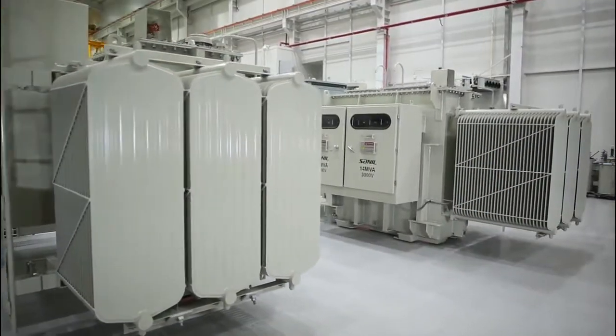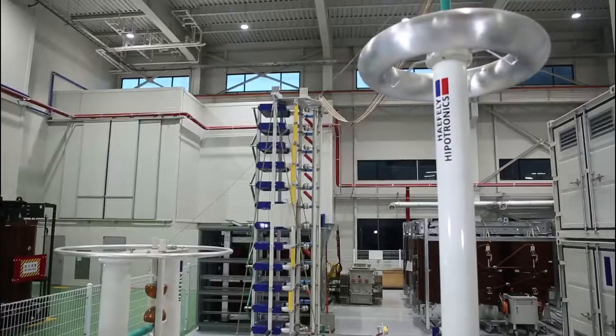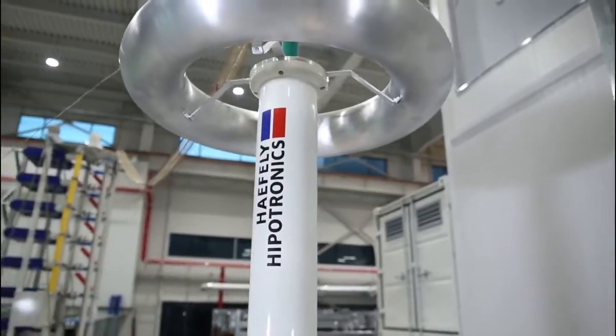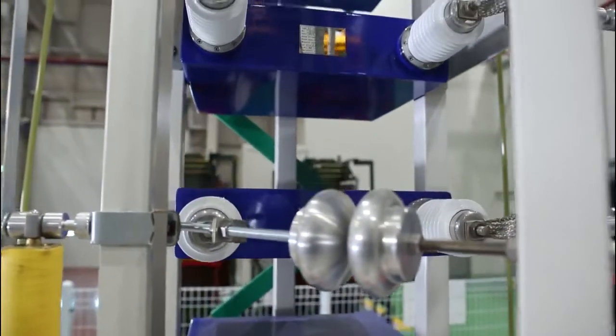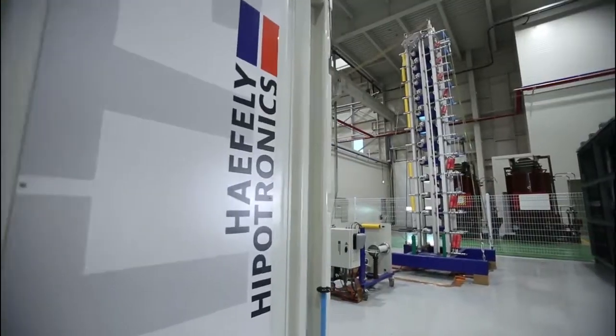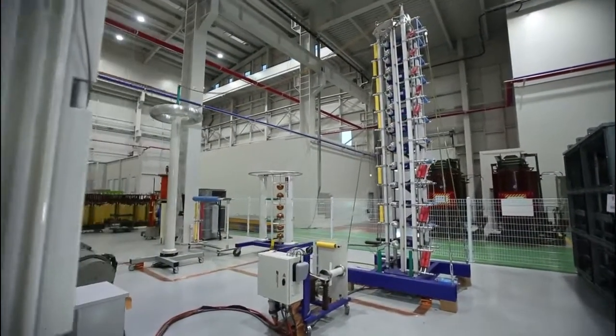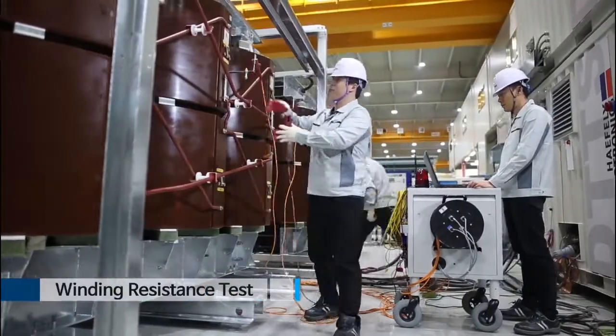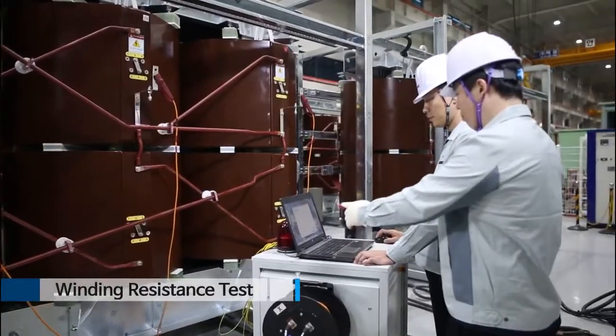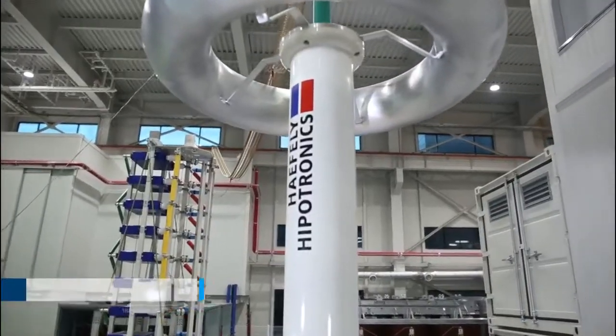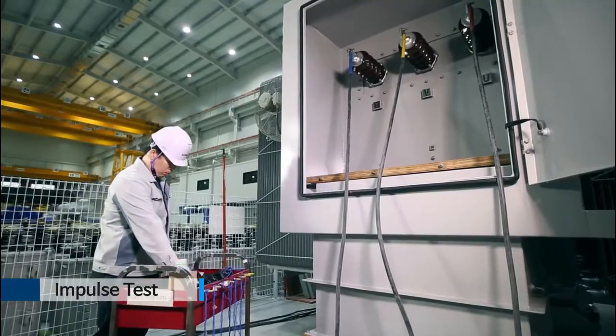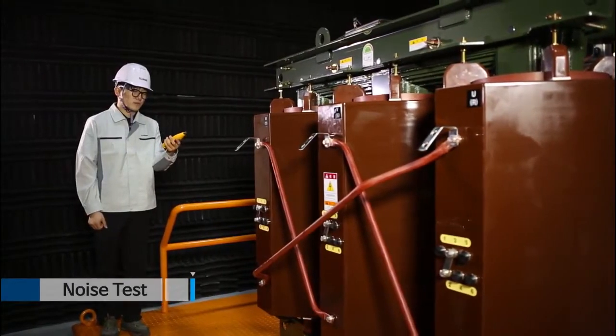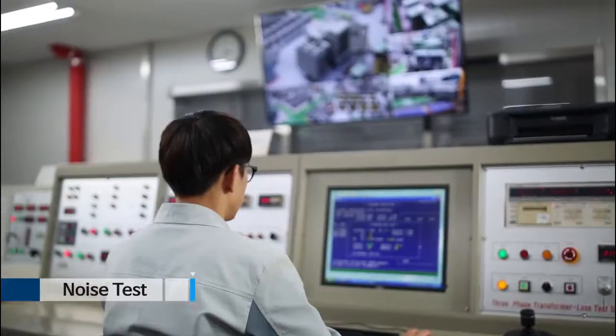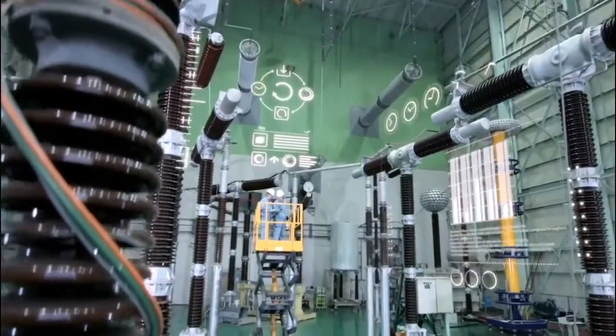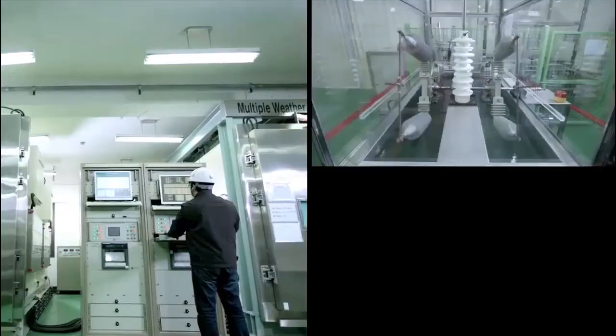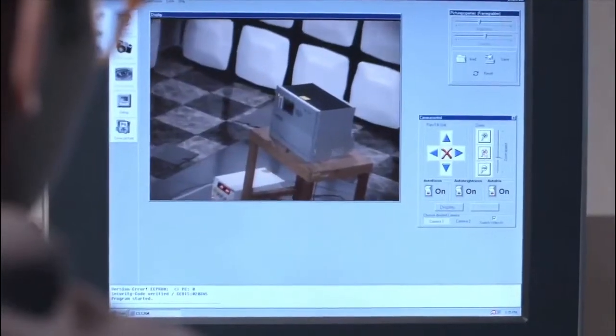Sanil products are individually tested based on international standards as well as customers' demands. And they become 100% reliable products which satisfy customers' demands. All transformers are tested in 8 categories of routine tests, which include coil resistance and voltage ratio measurements, which are requirements of customers and the IEC and IEEE international standards. Lightning impulse, temperature rise tests, and sound level tests are performed in the type test. All tests are fully performed with its own testing facilities and equipment. The short circuit tests are performed in accredited testing laboratories such as KERI, KEMA, CESI, UL, etc.